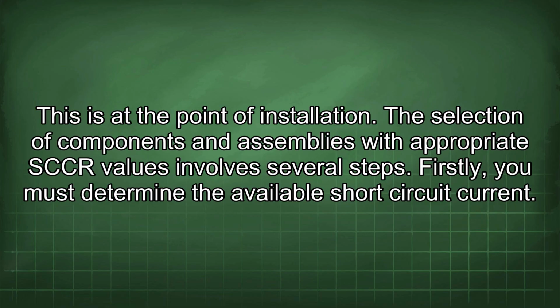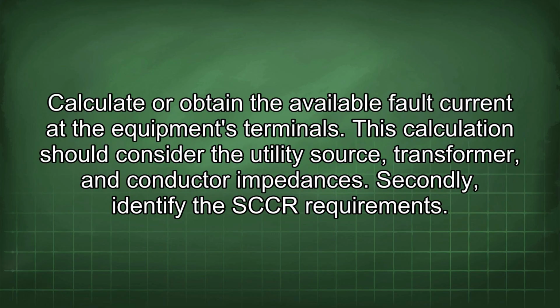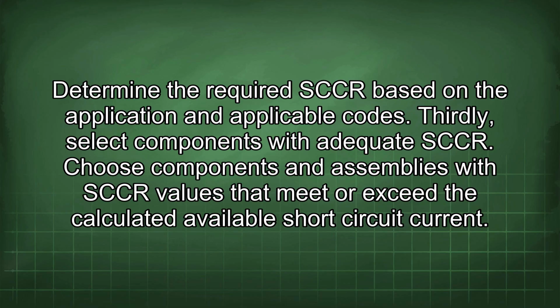The selection of components and assemblies with appropriate SCCR values involves several steps. Firstly, you must determine the available short-circuit current. Calculate or obtain the available fault current at the equipment's terminals. This calculation should consider the utility source transformer and conductor impedances. Secondly, identify the SCCR requirements. Determine the required SCCR based on the application and applicable codes. Thirdly, select components with adequate SCCR. Choose components and assemblies with SCCR values that meet or exceed the calculated available short-circuit current.